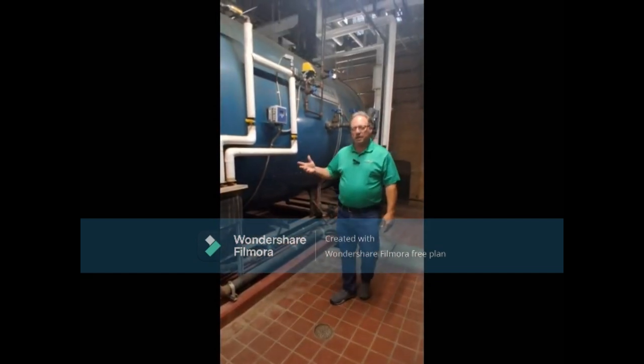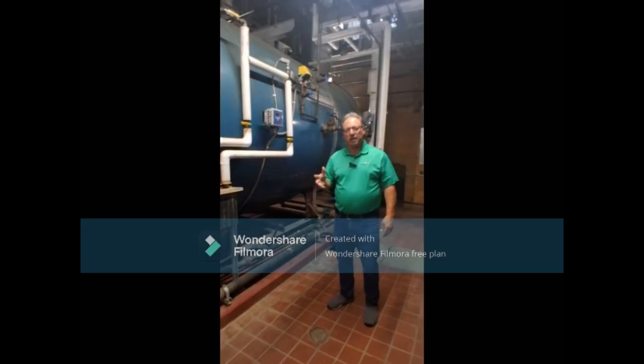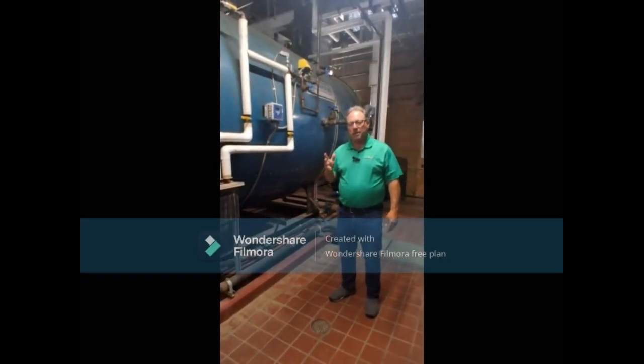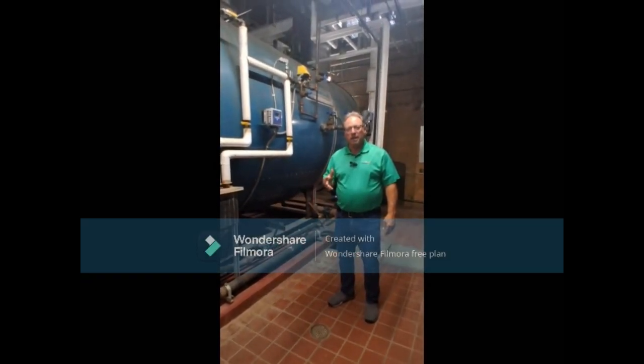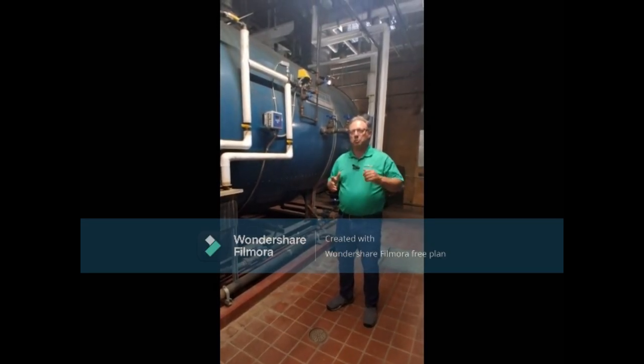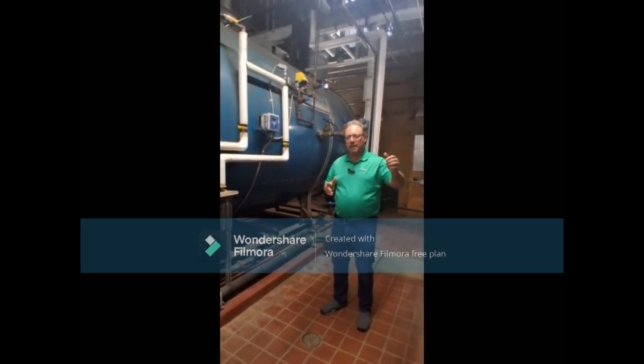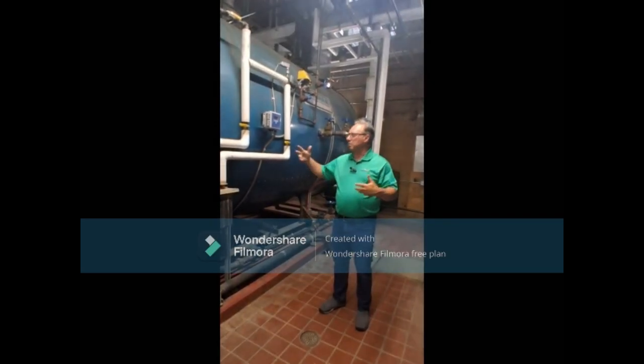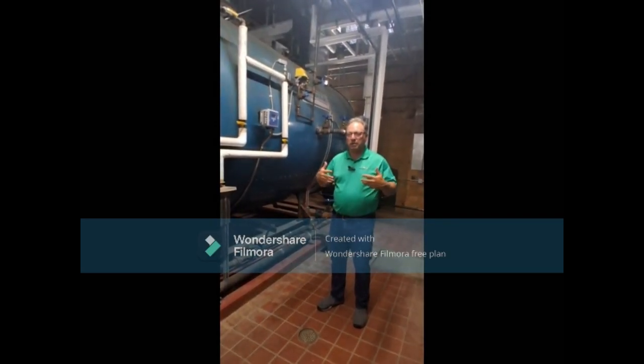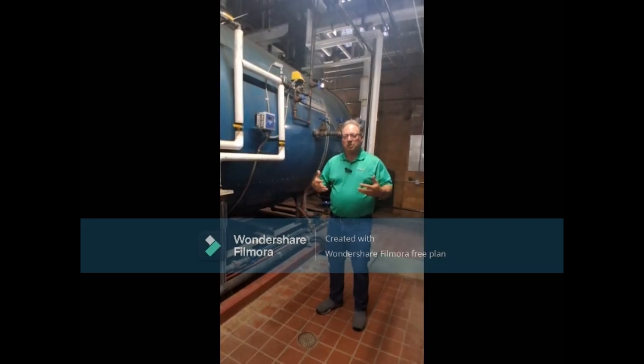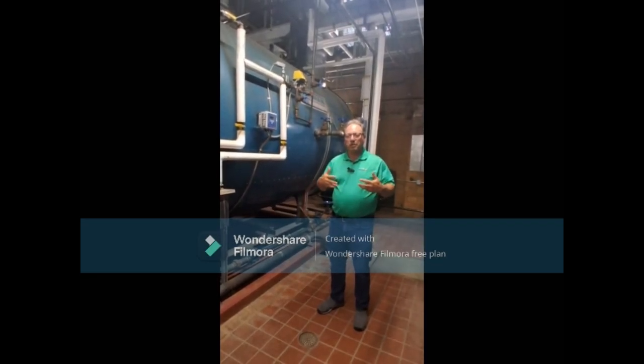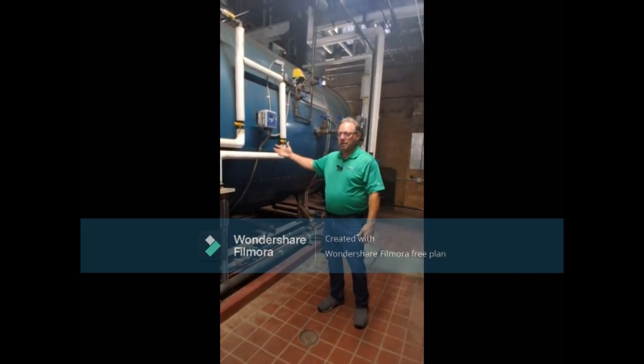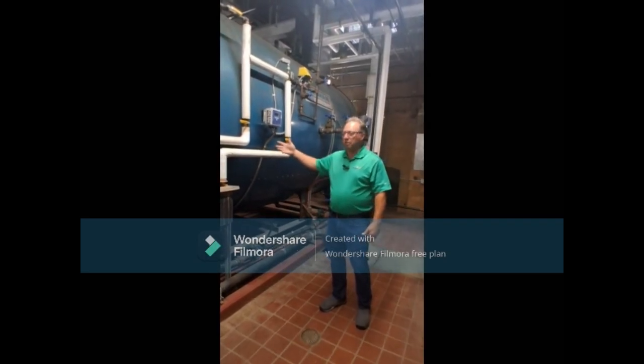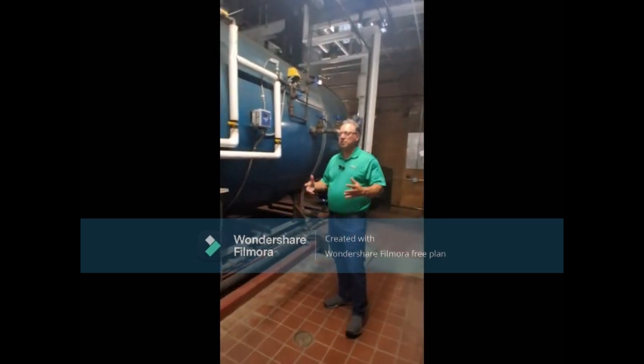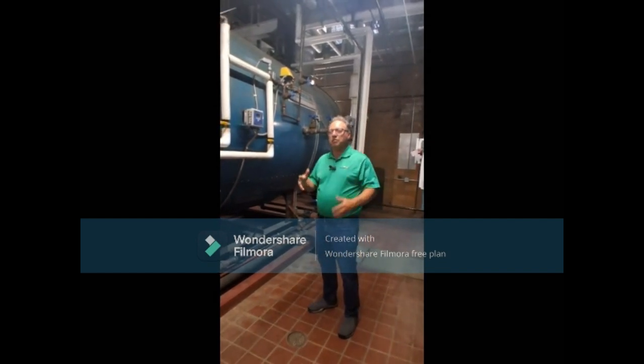We're at boiler number 1 here, and what's unique about Scale Free Systems is that we protect all heat transfer equipment. Other non-chemical systems just rely on the cooling side, and they can't treat heat exchangers or boilers like we do. So we actually are a full service on non-chemical for all heat transfer systems, like a boiler. You never see a non-chemical system on a boiler. So Scale Free Systems is a non-chemical physics-based water treatment.